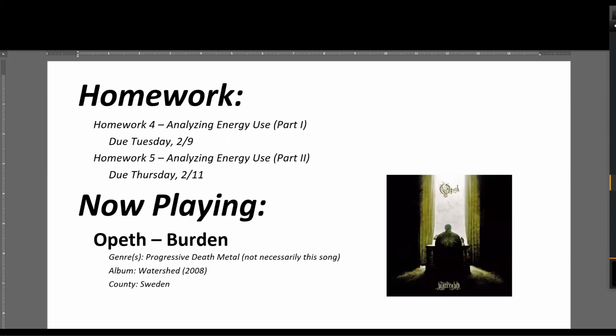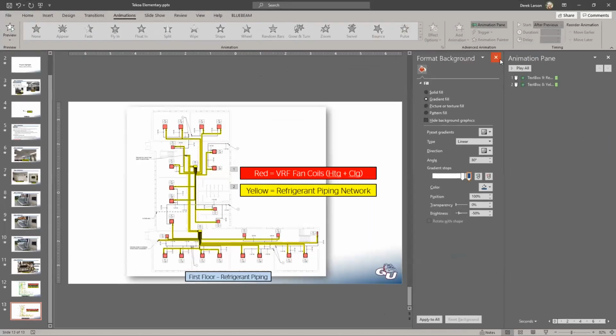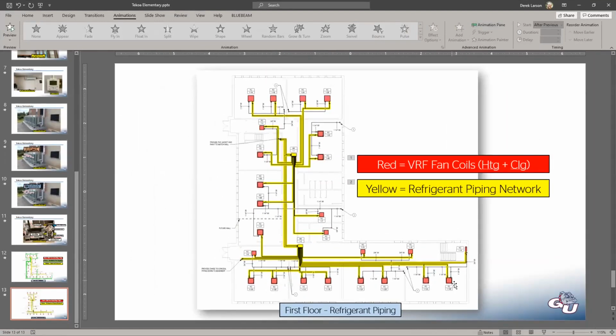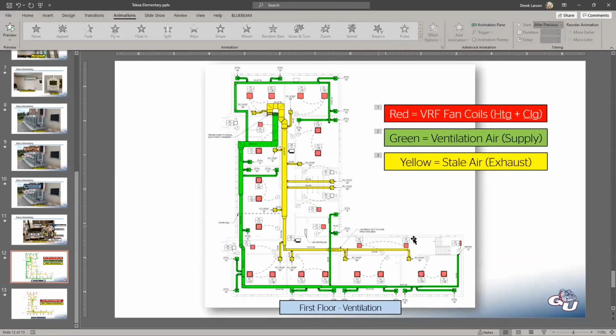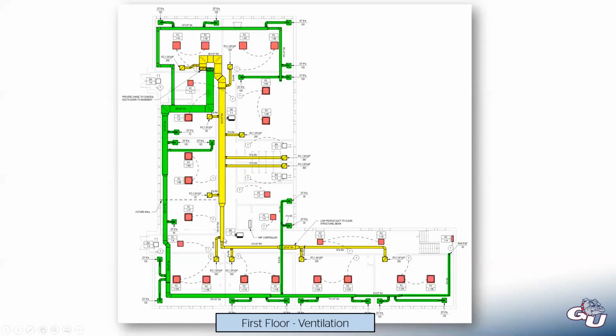Is that system mainly just used if different zones are going to be in different operating modes, like cooling or heating? Right. At any given moment, you can have zones in heating or cooling. Another feature that's neat about this is that a lot of times with a heat pump system, the heat pump can only operate in heating or cooling. What this system can do is these can be in cooling, these can be in heating. You can have a mix and match through the entire building, which is a little unique because normally you can't do that. Normally it's, well, we all got to be in heating or we all got to be in cooling. If somebody's not happy with that, well, they're just going to get a little uncomfortable.